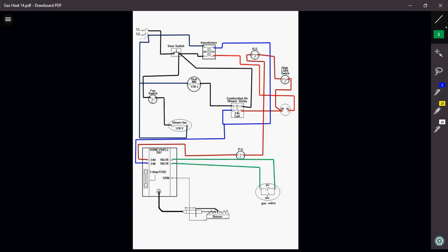So really the sequence of operation of this type of furnace is once my thermostat calls for heat, my inducer motor is going to start to spin. Once my inducer motor spins, my pressure switch is going to close. And as long as my other safeties that are in my furnace are closed, because your high pressure switch, your high limit switch, your rollout switches are all normally closed switches. The only way that they're ever going to open is in the event of either a high limit problem or a rollout problem. Now, a rollout is when the flame rolls back out at you. Instead of going into the furnace like it's supposed to, it rolls at you. That's a rollout. Again, that could be caused by a couple of problems.